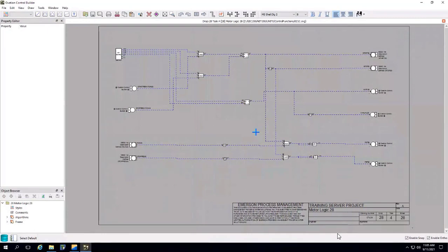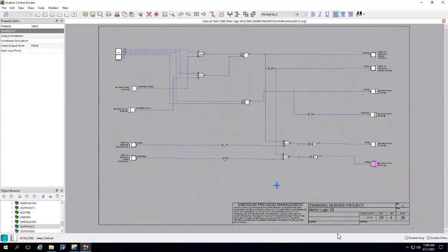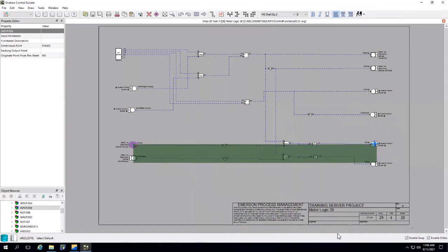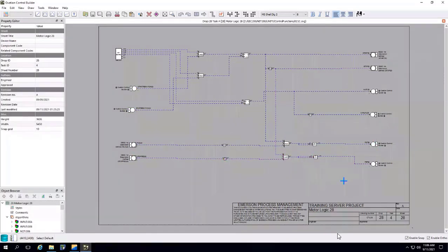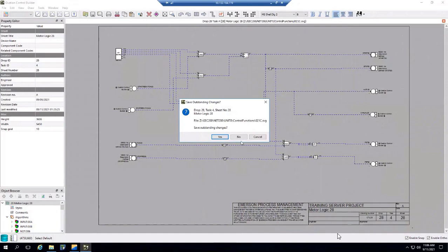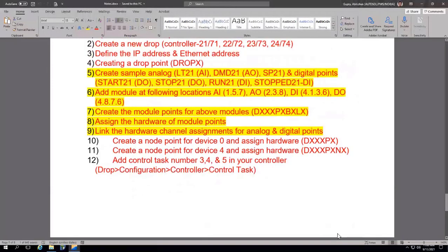Okay. So whosoever is testing, implementation is good. He needs to define the point names along with the descriptions is missing and alarm is missing. Rest implementation is good. Just he needs to write the point descriptions and alarms for these 2 points. Name and number is perfect. Right? Point description and alarm description. Okay. Yes. Clear. Okay. So we have completed this job.